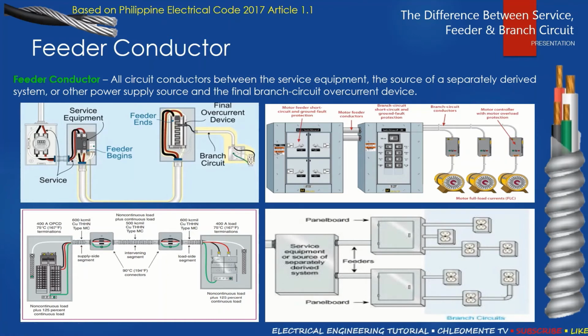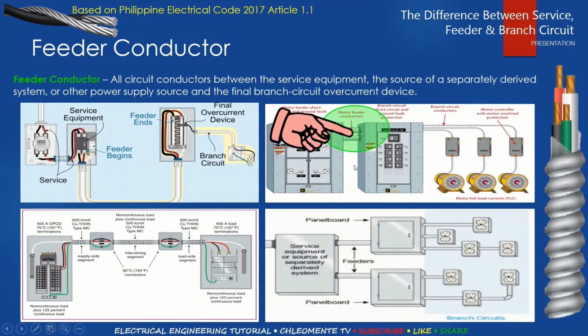Feeder conductor naman, ito naman yung circuit conductor between the service equipment and the final overcurrent device. The conductor between the service equipment at saka yung isang feeder. Okay, so feeder conductor. So itong conductor between your service equipment at saka another overcurrent device, yan ang tinatawag na feeder conductor. So sa installation natin, normally yan. So may circuit breaker ka dito and another sets of overcurrent device panel. So tinatawag na motor feeder conductor kung motor ang load mo.